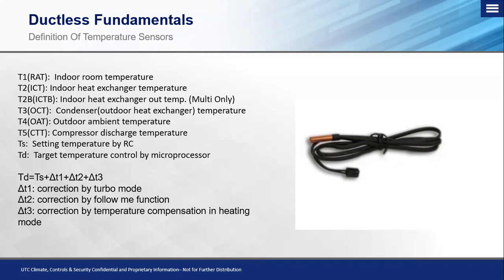Now we look at our TS on there, which is the setting by the remote controller. That could be a wired remote controller or a wireless remote controller. So the setting temperature by the customer is going to ultimately play into how the system needs to figure out where it needs to run at. Now, all of that feeds into our TD, which is the target temperature controlled by that microprocessor. You look at that and go, whoa, what does that mean? All that means is it's taking in all this information from the indoor and from the outdoor unit and figuring out, we'll call it a sweet spot of where it needs to be at and where it needs to run and how it needs to change as the system starts running and getting the temperature close to the set point. So it's looking at all this information and making logical decisions.